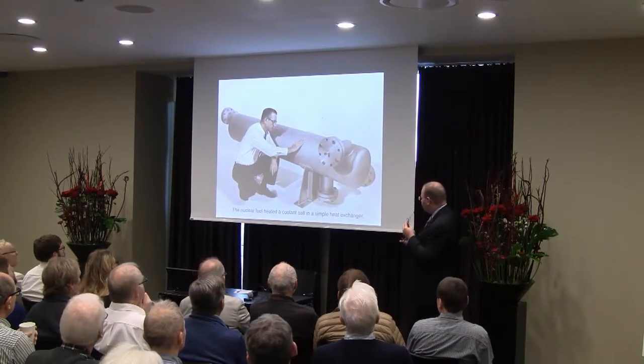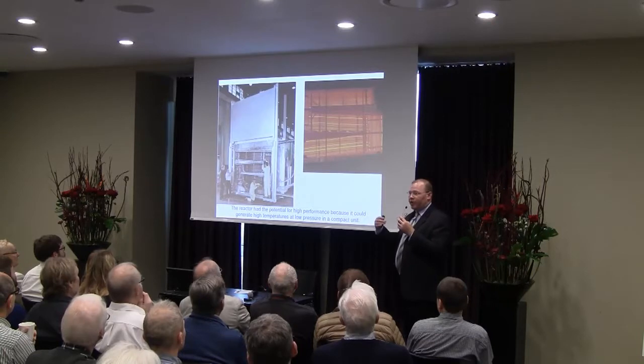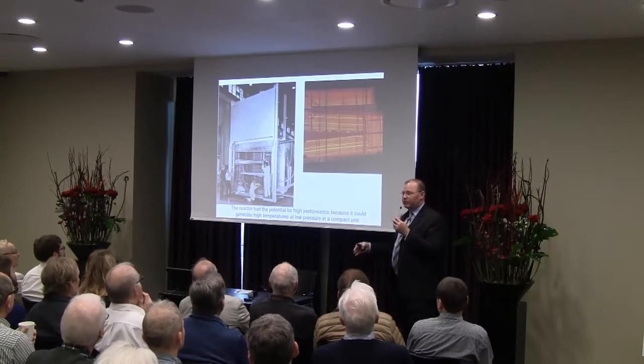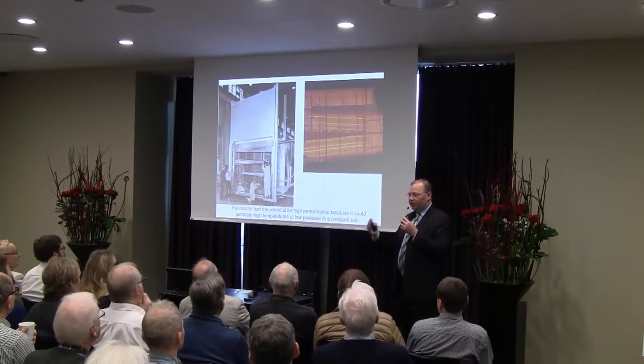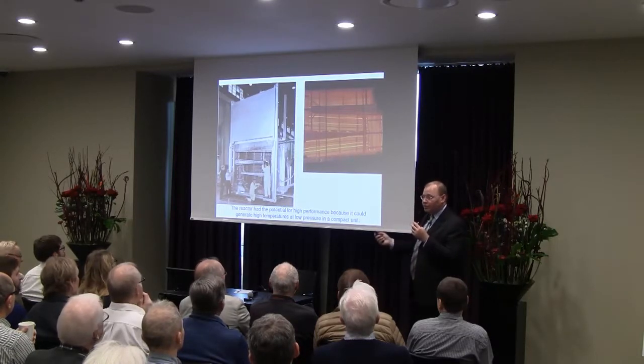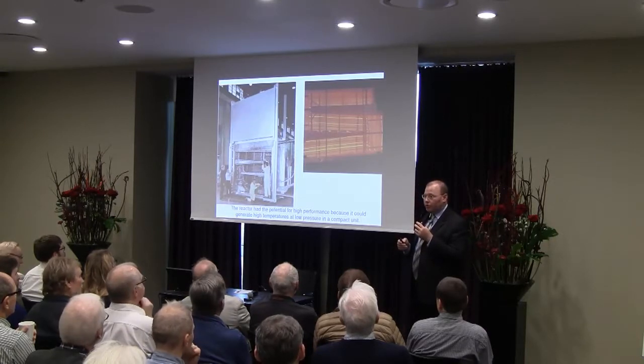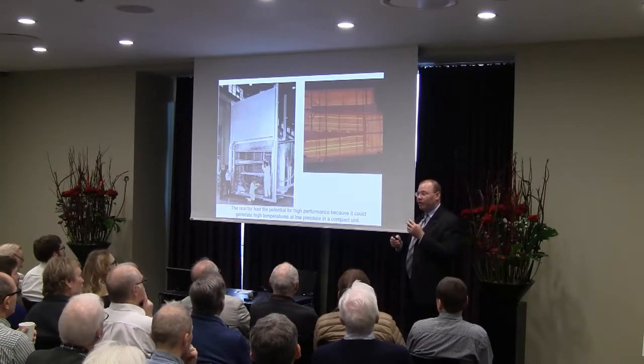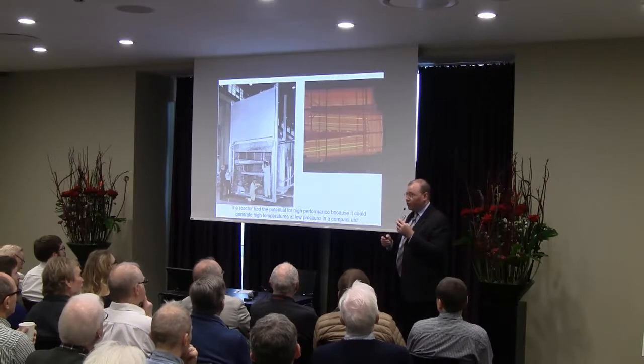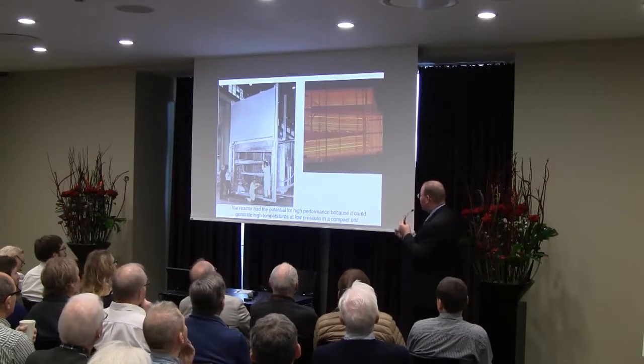Here's a picture of the primary heat exchanger to the reactor. The thermal energy was just dumped to the environment — it wasn't put through a power conversion system, because this was simply an experiment and they weren't trying to make electrical energy. But in principle, had this been coupled to a power conversion system, it probably would have been able to generate electrical energy at 40 to 45 percent efficiency, which is really spectacular — and it's because of the high temperature.